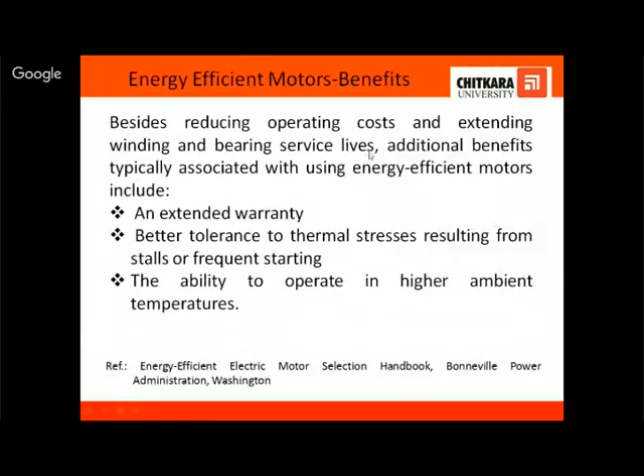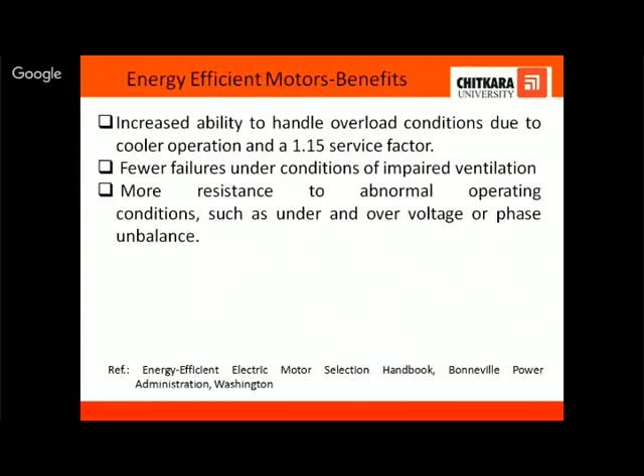Now energy efficient motors have many more advantages. One thing is that operating costs are less, and additional benefits are that they have an extended warranty and better tolerance to thermal stresses resulting from stalls or frequent starting. These motors have the ability to operate in higher ambient temperatures. Then they have increased ability to handle overload conditions due to cooler operation, and the service factor is 1.15. So it means they can run at 15% overload without temperature rise.